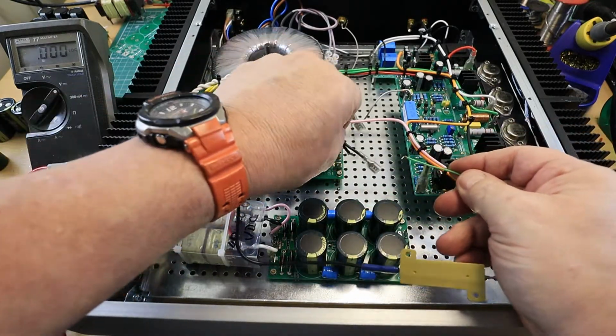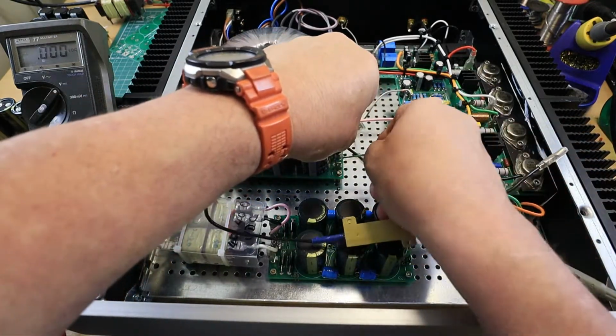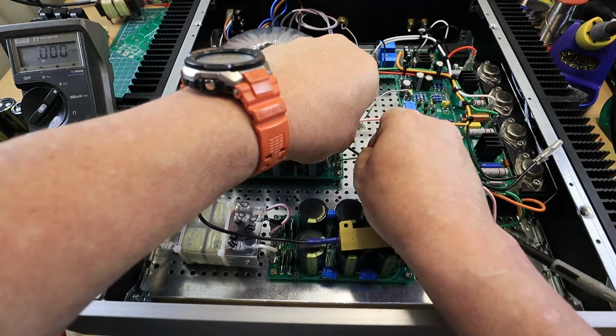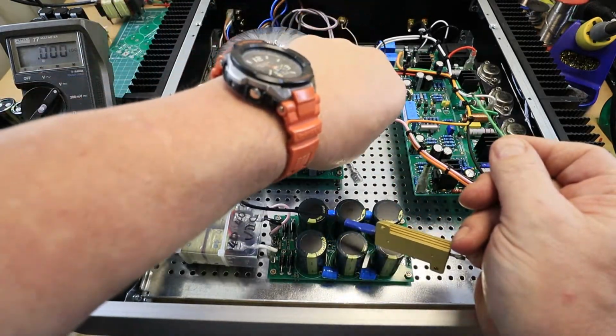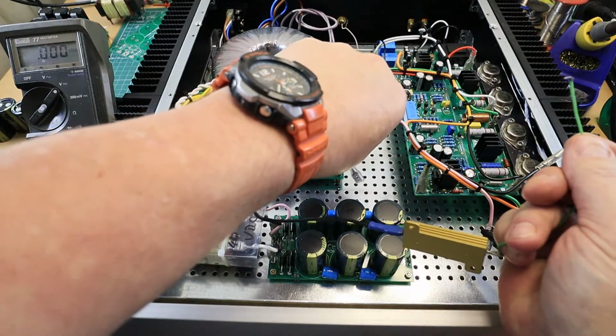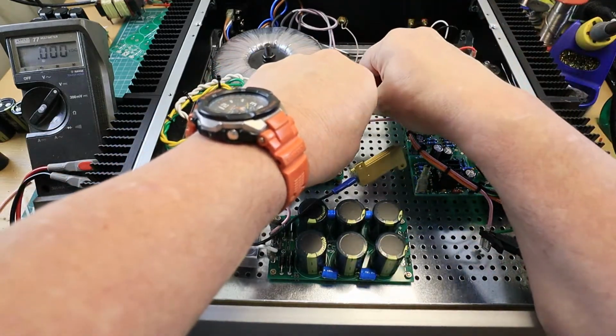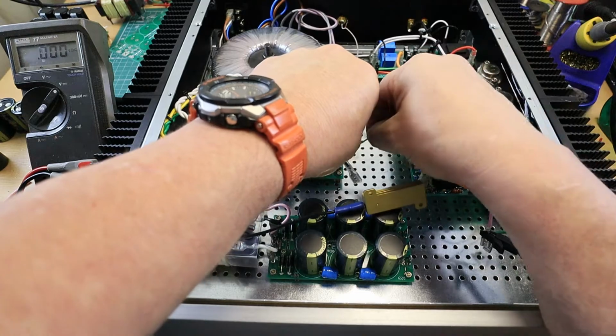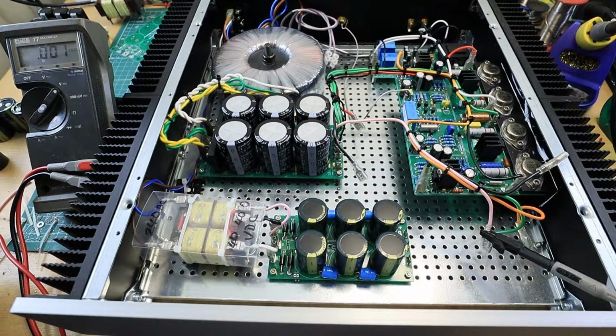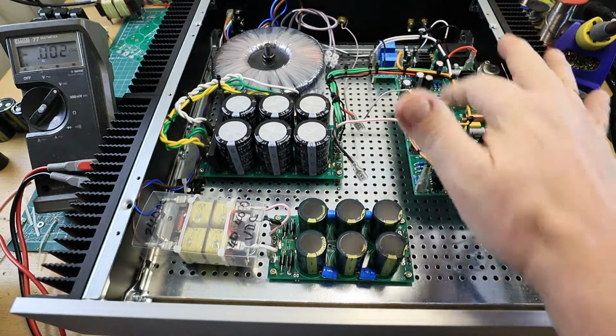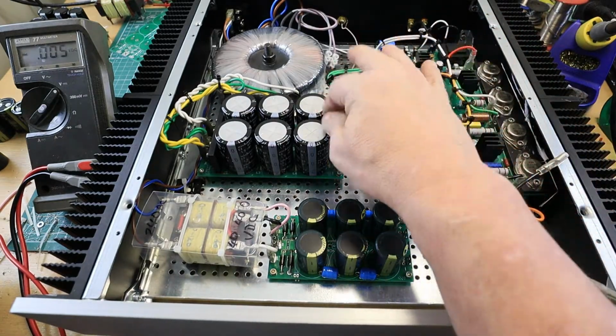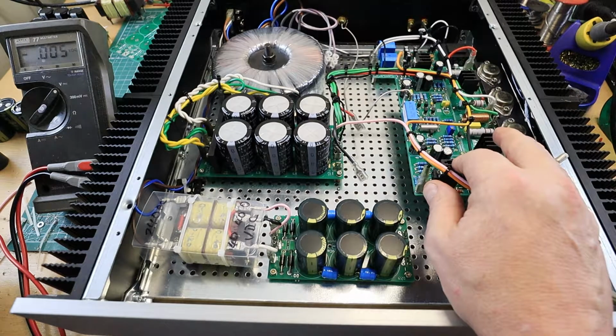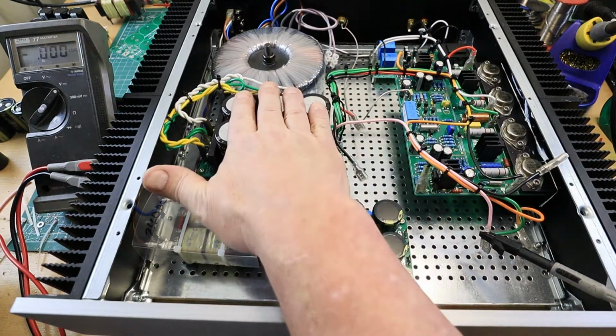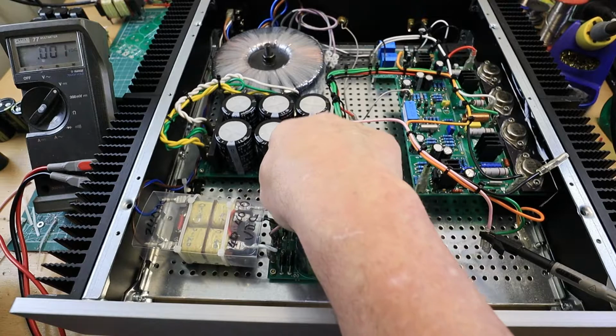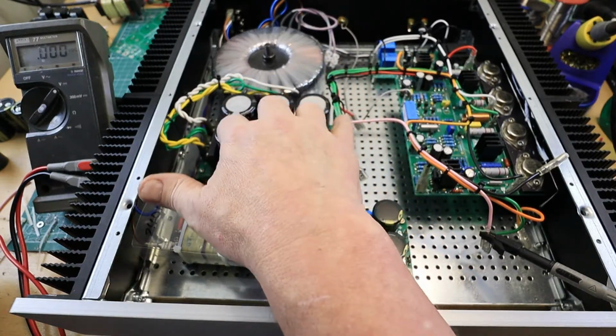This one will be a bigger spark, because what you don't want to do, there you go, you don't want to connect these energized power supply units to your amp board when they're charged, because you get a surge. It might only be millivolts, but you get a surge the wrong way. 0 is 0, that's connected. But if these weren't discharged, there's some resistors in the bottom of this, so this bleeds off quite quickly, within 2 or 3 minutes.